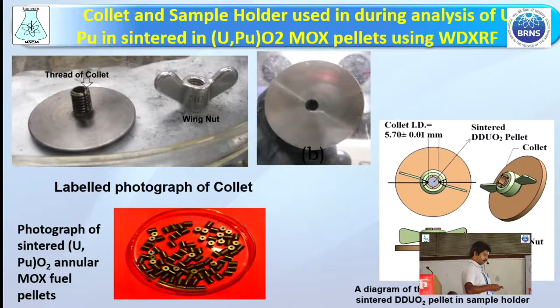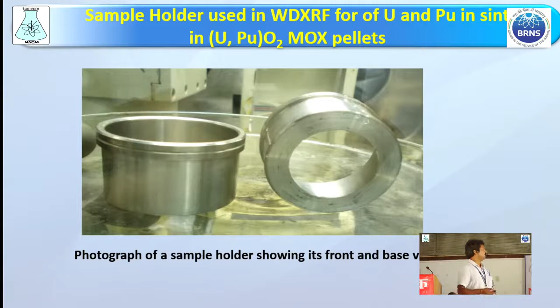Here we have a collet. We insert these pellets inside this hole and, using this wing nut, we tighten the samples, and we put this collet along with the samples in a sample holder. This is our sample holder of size 44 mm, and the cutout is 40 mm. We need this collet so that it can be held in the sample holder and our sample does not fall in the spectrometer. Then we send our sample holder along with the sample into the spectrometer to get the uranium and plutonium L alpha intensity.